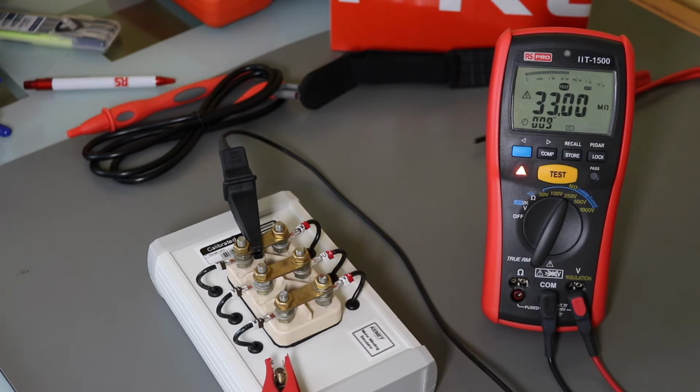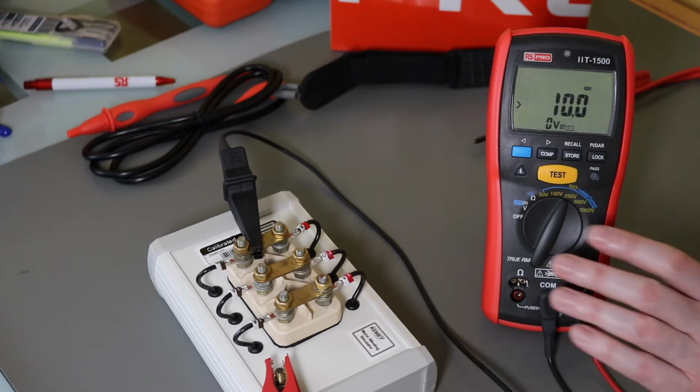Some people will discharge it for up to 4 times the amount of time you had the test applied for, so you know there's no interference between the 2 tests. So you can see originally it came out as 7.1, it's come out as 10 now, and that's the reason why, when you do this, if you don't discharge between tests, you can affect the test result. But 10's quite high.